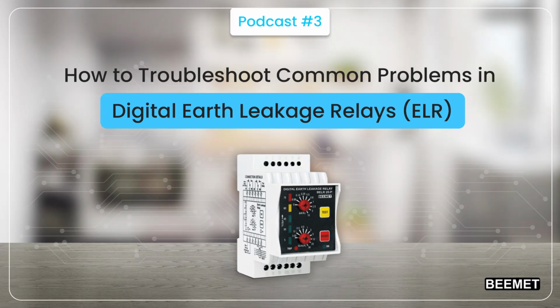Communication or display failure. Such failures include blank screens and broken buttons. There will no longer be any monitoring available. What to check? Restart the relay fully. Confirm supply stays within 110 to 240 V. Test RS 485 and keys with a loopback.